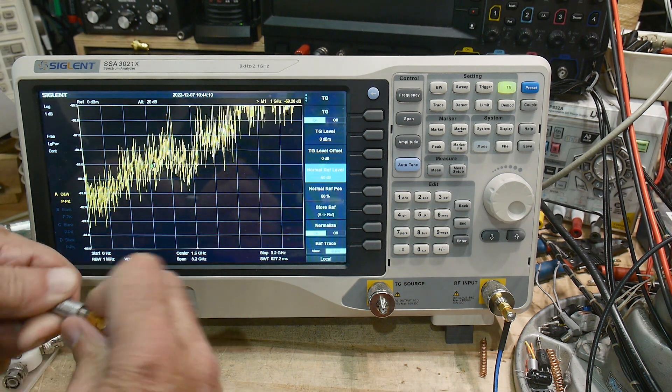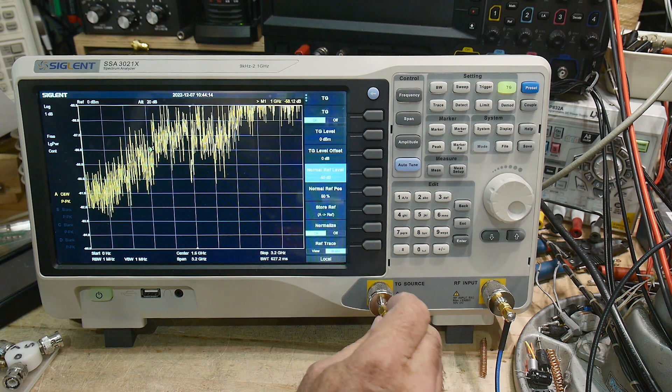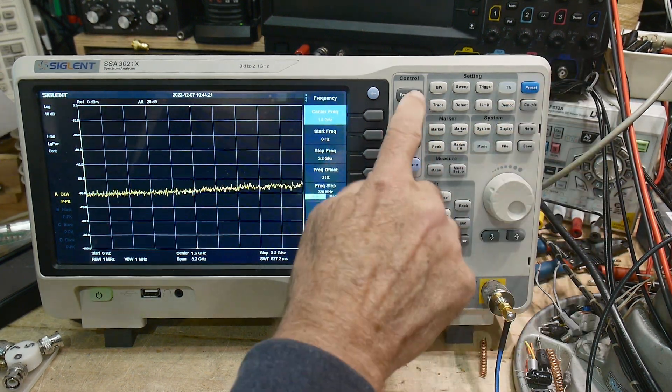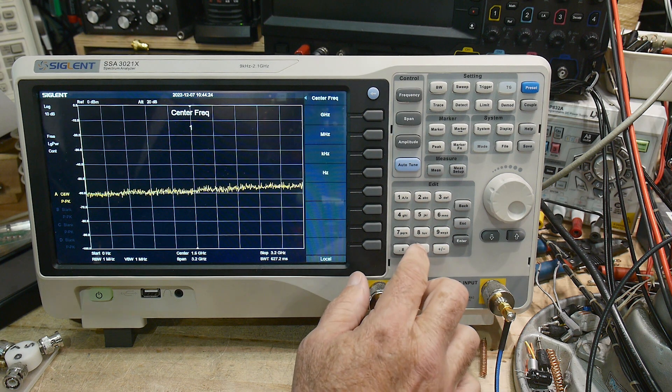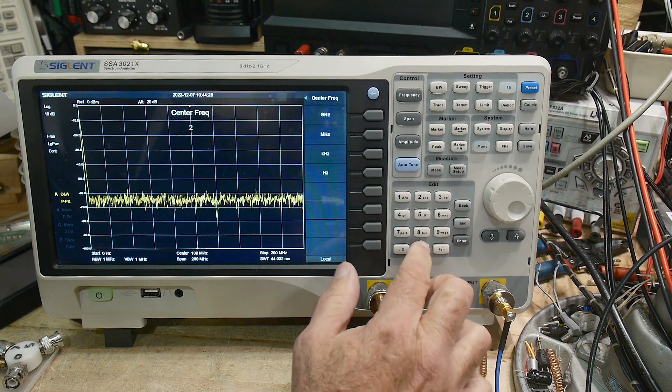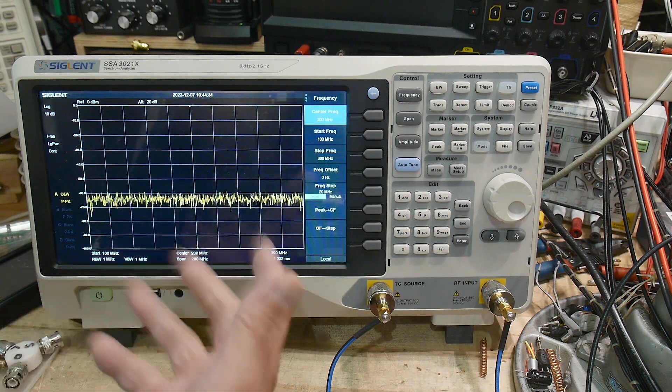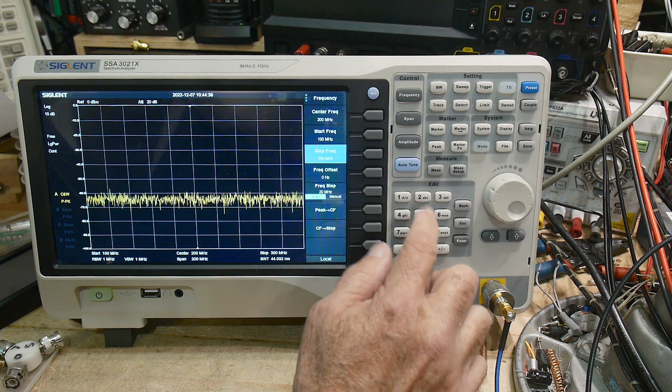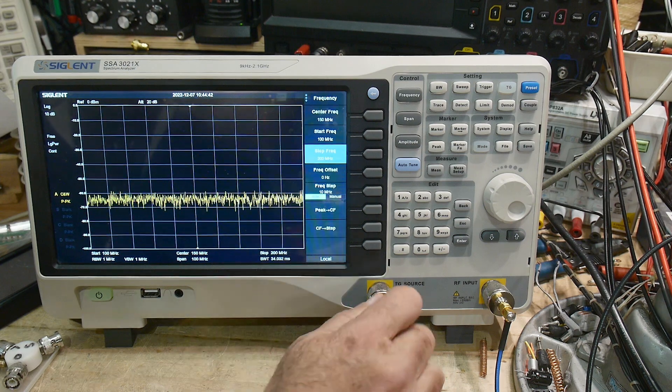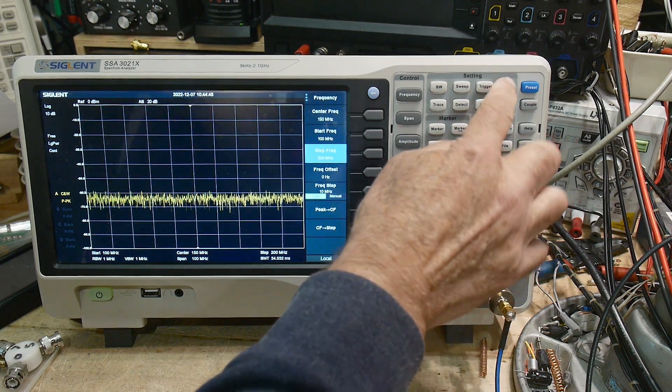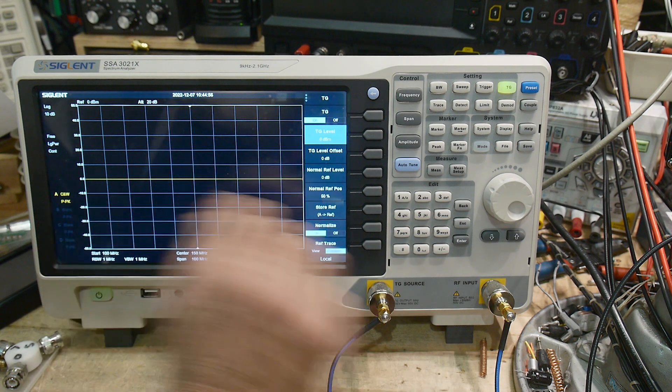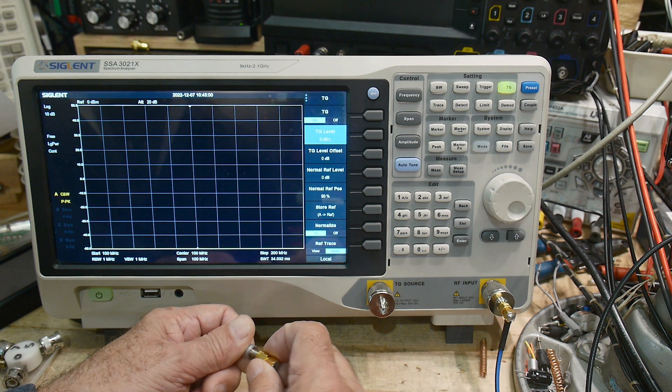This attenuator is good to 12.4 gigahertz, but I think we can do a little bit better here. Let me do a preset. I'm going to set our frequency from 100 megahertz to 200 megahertz. Let's say I'm going to be measuring something around 144 megahertz, so I'm going to go between zero and 200, stop frequency 200 megahertz. Zero to 200. I'm going to turn on the tracking generator, set my output level to zero, store it and normalize it, so now they're at zero.